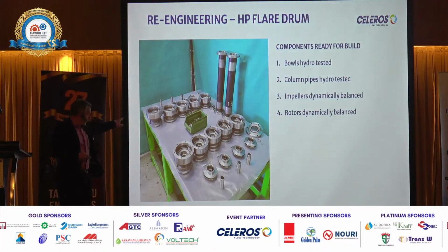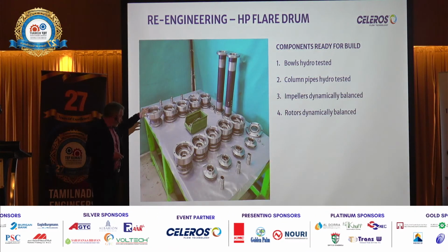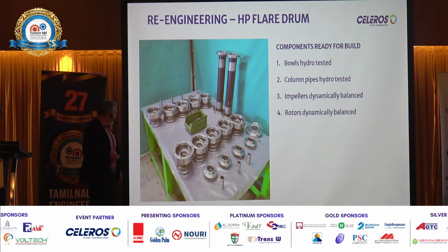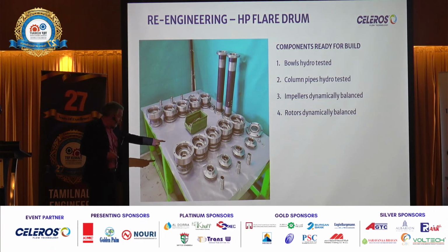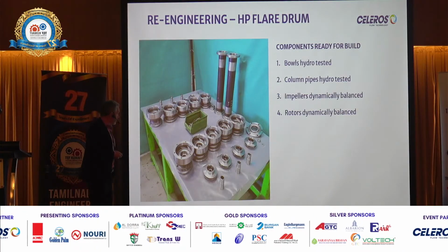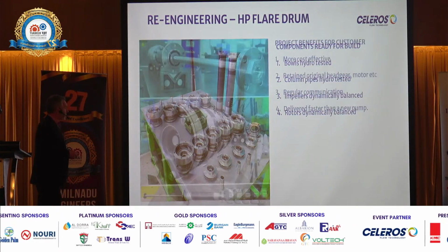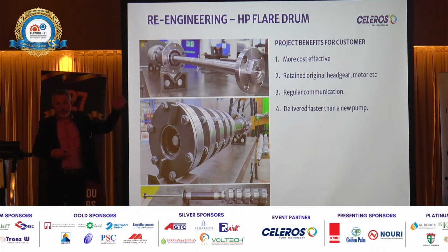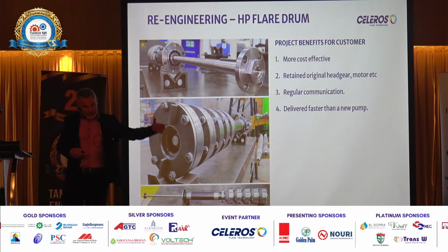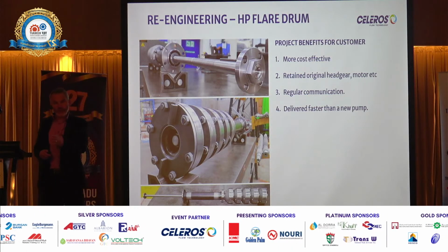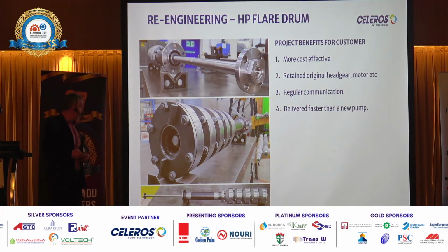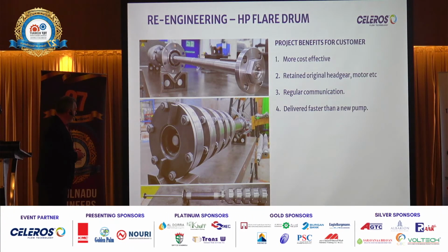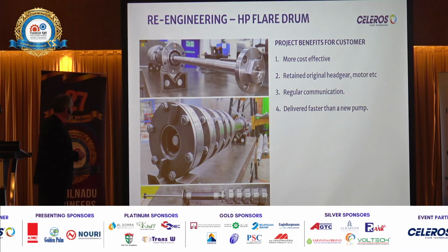These are all scanned, so we've manufactured them. So we've actually reverse engineered, re-engineered it. All the impellers, shaft sleeves, diffuser bowls. And again, this all goes through our own QA system. So as soon as we've scanned it, the procedure starts. We just follow it as if it's an OE pump. It goes through all the QA procedures. We hydro test, we dye pen, we do any ultrasonics.